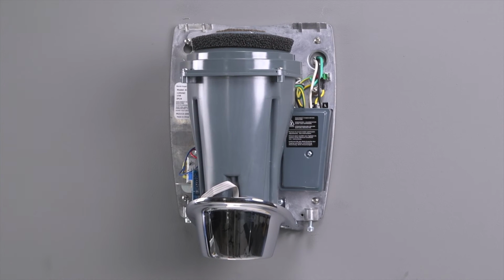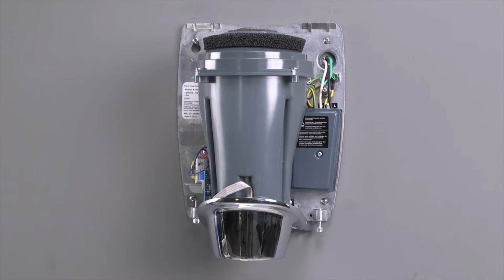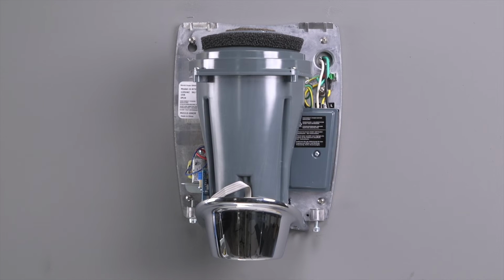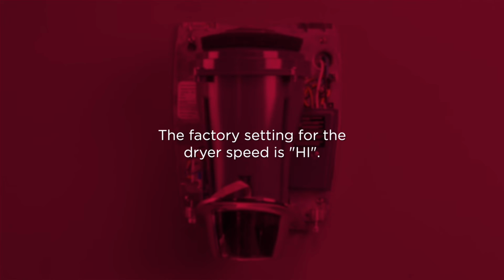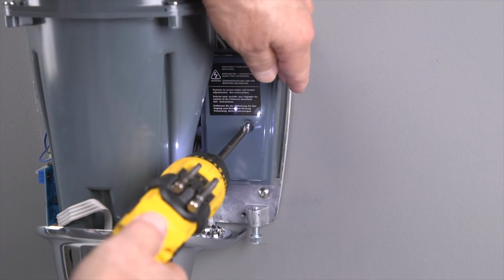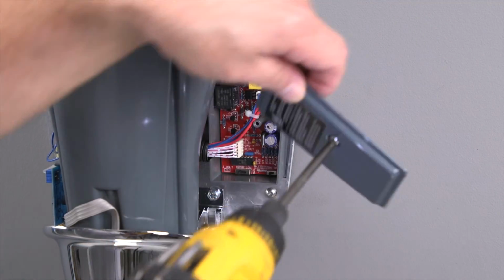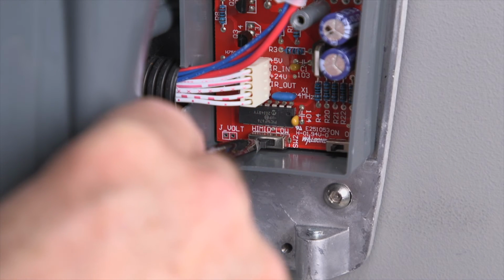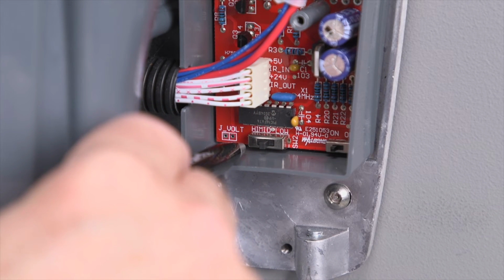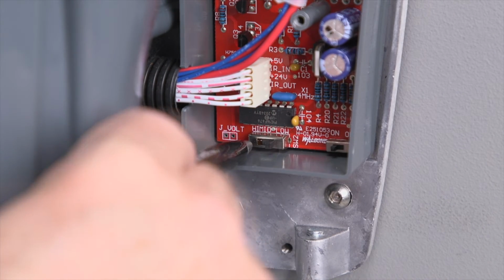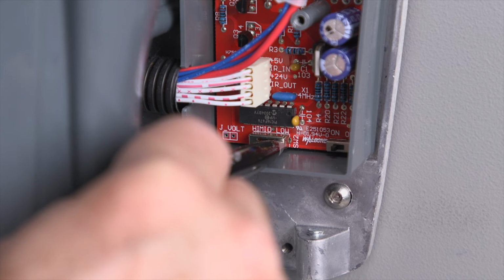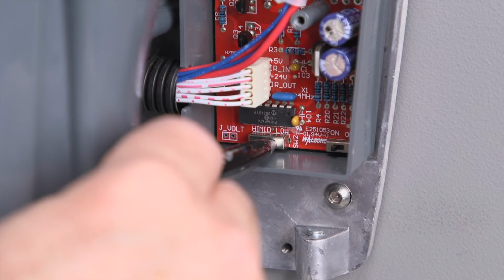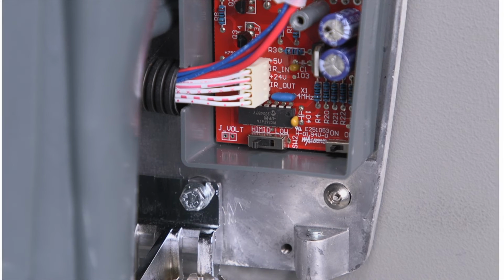If you've diagnosed that the dryer is too loud or too slow, you'll need to adjust the dryer's speed. The factory setting for the dryer speed is high. Remove the wiring compartment cover to access the adjustable controls. If you've diagnosed that the dryer is too loud, select a slower dryer speed. If you've diagnosed that the dryer's air output is too slow, select a faster dryer speed.